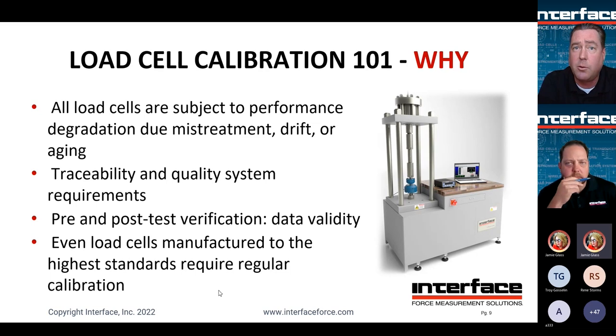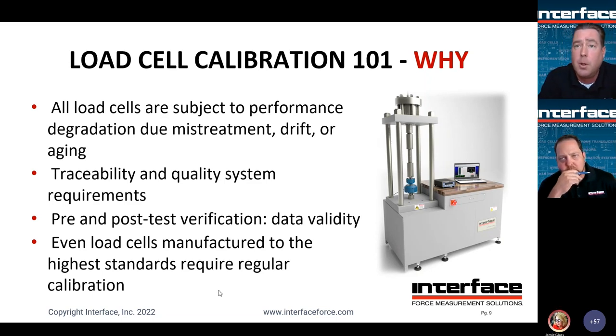Marcus, I see a couple questions that are pretty good there. We do perform some adjustments to the load cells during the manufacturing process, primarily our low profile load cells. And that's primarily based around moment compensation. So you could view that as a calibration in a way. However, it's slightly different than our final calibration process that defines the actual sensitivity of the load cell. It's more like optimizing the load cell through the production process, I would say.